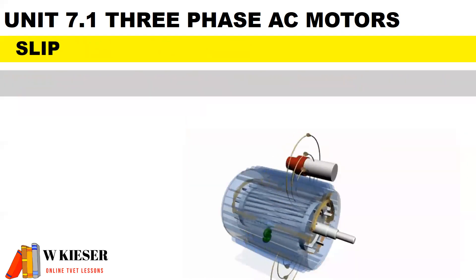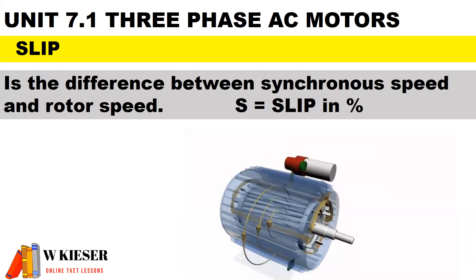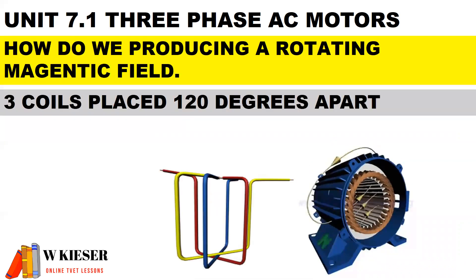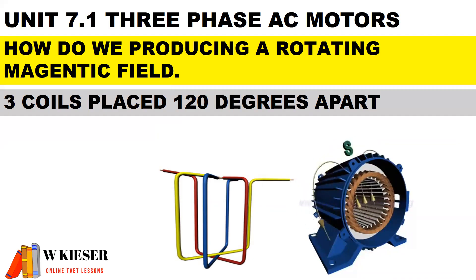What is the term slip? Slip is the difference between synchronous speed and rotor speed, and is represented by a percentage — the symbol is S. How do we produce a rotating magnetic field around the stator? Three coils placed 120 degrees apart means that when current passes through the coils, they'll also be out of phase with each other by 120 degrees. The magnetic field set up by each coil is combined to produce the rotating magnetic field, and this rotates at synchronous speed.